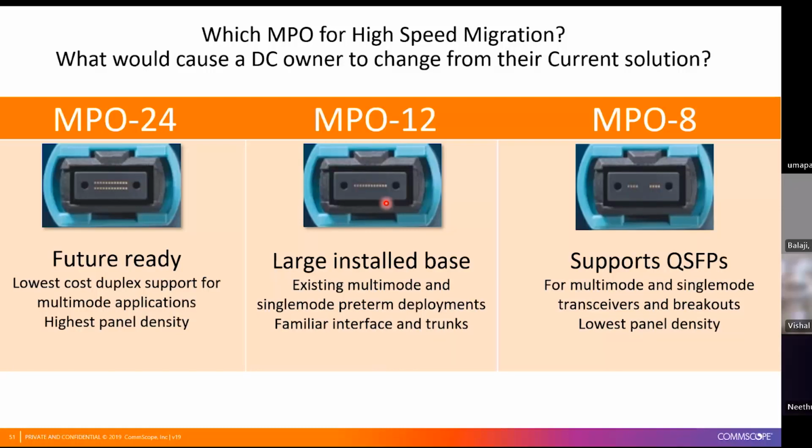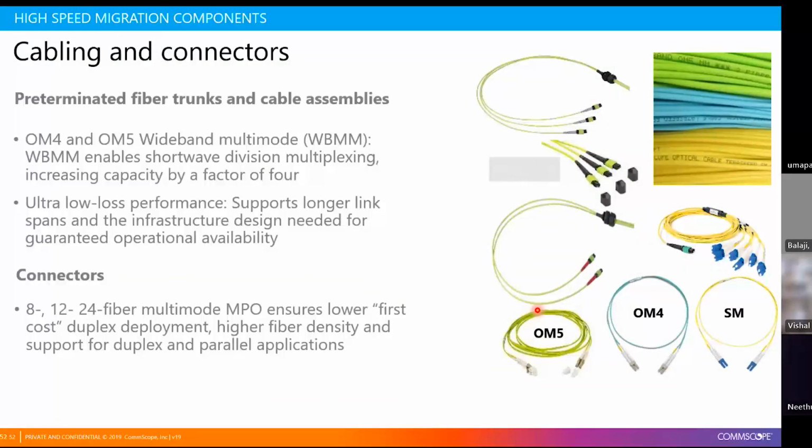When you want connectivity between racks, we have a trunk cable which comes in 12 fiber as well as 24. So for any connectivity inside the data center in future, there won't be any splicing or manual termination. It's purely trunk cable connectivity. Here you can see the trunk cable, MPO 8, 12 or 24. Let's say you want to connect rack 1 and rack 2, and the distance is 30 meters. You don't need to lay 30 meters of fiber cable and do the splicing and everything.